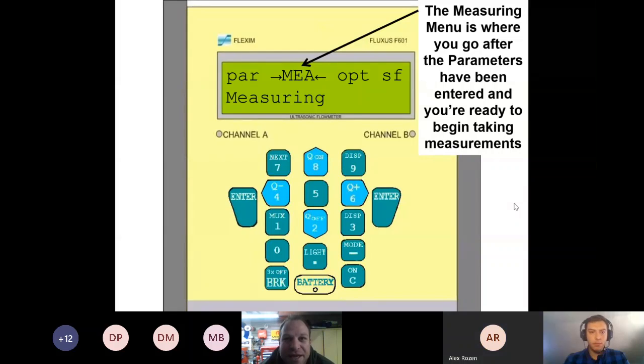And when you put that in there and you check that sound speed parameter, that will tell you if you have the correct parameter or not. So if you put in the ductile iron and then you find out that the sound speed's off, and you put in the double cement line, try the single cement line, and that might bring you in line. Also with wastewater, since you have solids and stuff scraping the pipe, they tend to wear out. So sometimes even if it started as a double cement line, it might not be one anymore. So you might want to play with that wall thickness and dial in your sound speed that way.